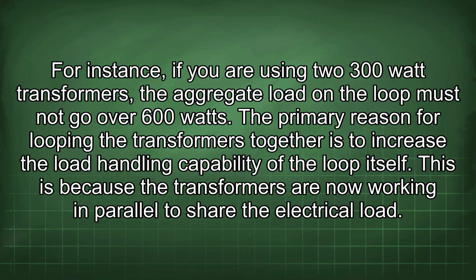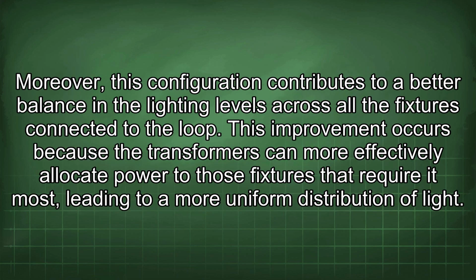watts. The primary reason for looping the transformers together is to increase the load handling capability of the loop itself. This is because the transformers are now working in parallel to share the electrical load. Moreover, this configuration contributes to a better balance in the lighting levels across all the fixtures connected to the loop. This improvement occurs because the transformers can more effectively allocate power to those fixtures that require it most, leading to a more uniform distribution of light.